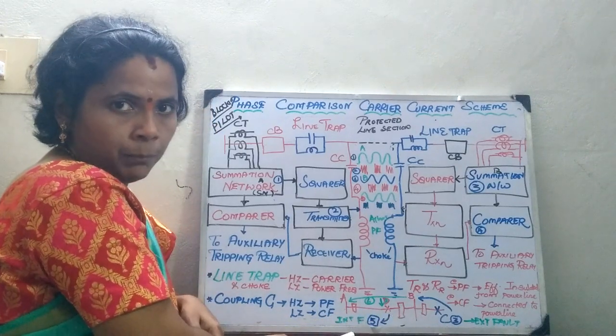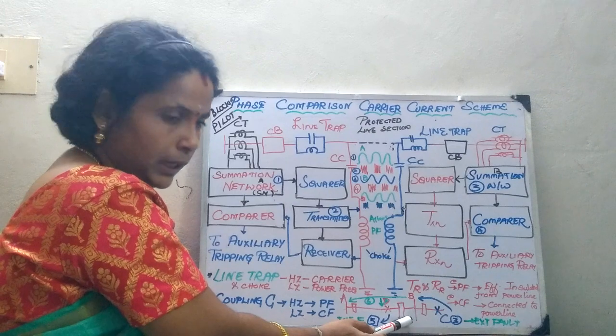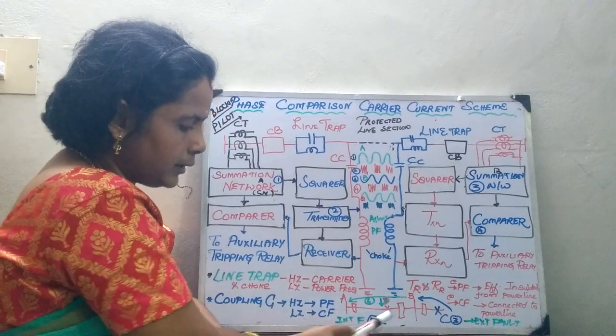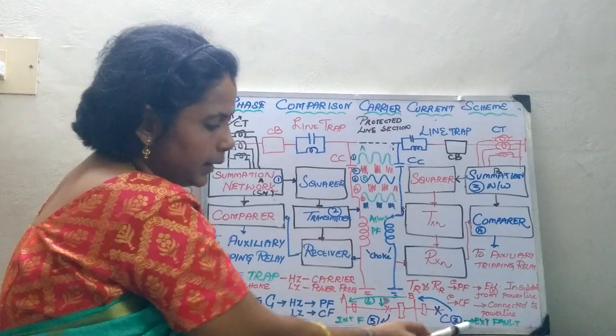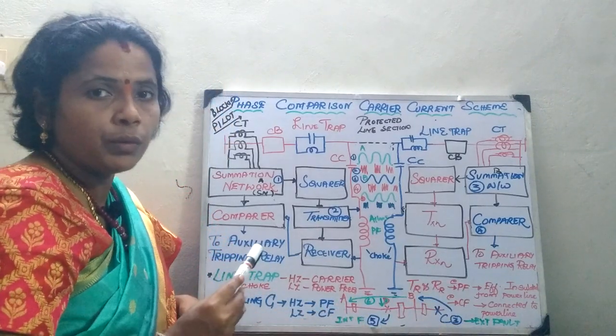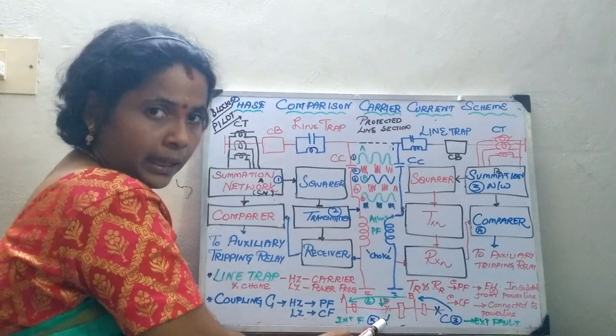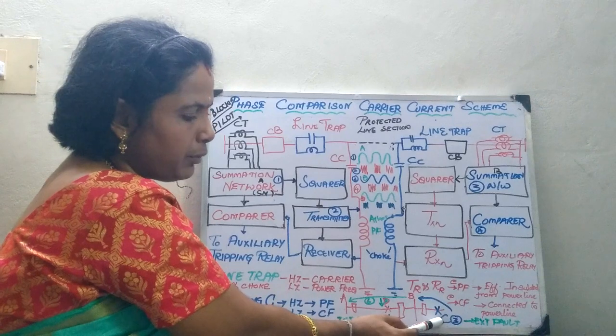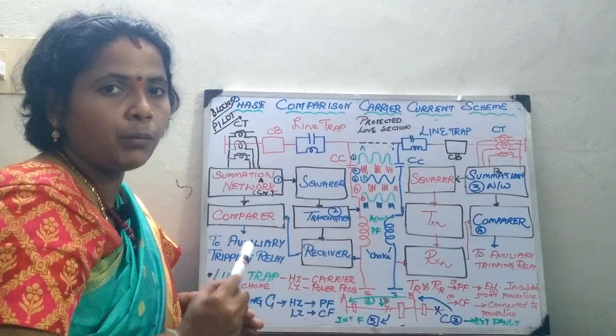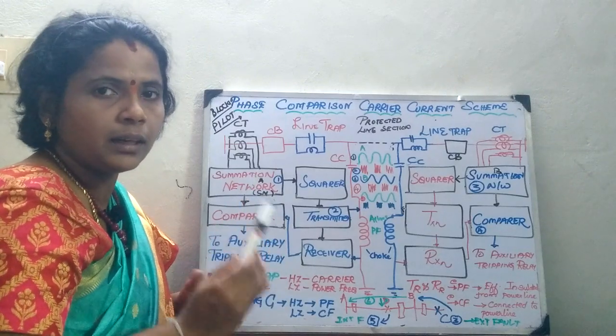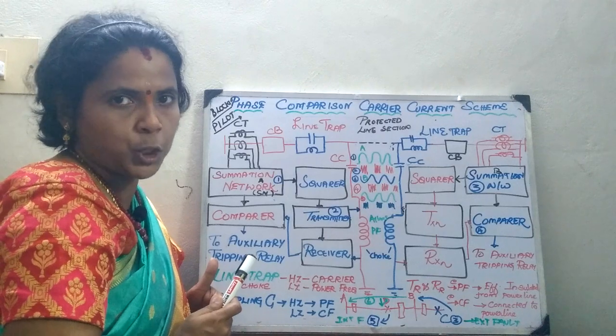Here I have taken an example: end A and end B of the line. I have considered an internal fault at point D and an external fault outside the line to be protected at point C. We will see how the relay operates for the internal fault at D but does not operate for the external fault at C, because the phase comparison scheme provides protection only within its designated zone.